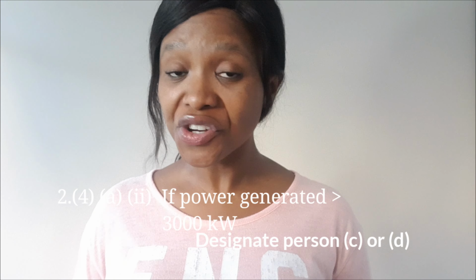So for power generation greater than 1,200 kilowatts and less than 3,000 kilowatts, you cannot have competent person A, someone with an apprenticeship in a trade, 5 years experience and 1 year in maintenance. That person is not the right person to supervise the machinery on your site. Where power generation is greater than 3,000 kilowatts, your competent person must be either C or D.